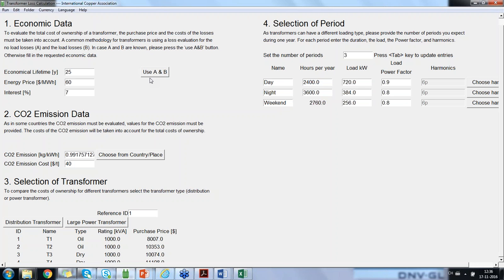But you have to provide him with the A and the B factor. In case you don't do it, he will definitely choose a transformer with very high losses, because he will be saving a lot of material in it. This program can calculate it for you, so in case you don't know it, feel free to play. In case you know your economical lifetime, you know your energy price, you know your interest, and also you know your loading profile, add it within this tool and try to play with it, because it's independent from the losses that the transformer manufacturer later on will provide to you. And within the results slide, the Word document I showed you below, there is already mentioned the A and B factor, which you can use within your request to a transformer manufacturer. I hope this answered the question.